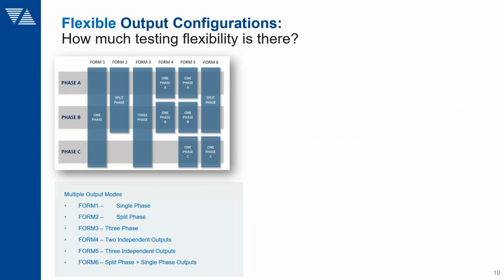Another important aspect is the flexibility of the grid simulator to offer different phase modes. And the most common phase modes, of course, are three-phase, split phase, and single phase. Most grid simulators will support three-phase and split phase. They may or may not support single phase, meaning you have all the power available in a single phase by having three phases in parallel. That in particular can be helpful if you're also doing DC testing where you may only need one voltage, but you need more current. So in the case of single phase, you can go to single phase mode and get all that power on a single phase in both AC and DC as you need it.